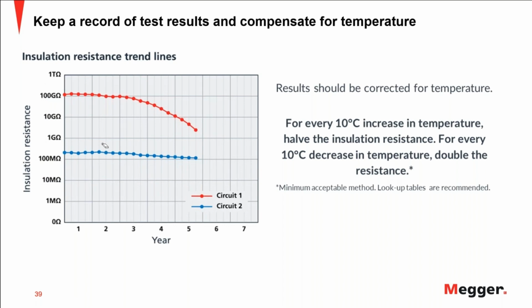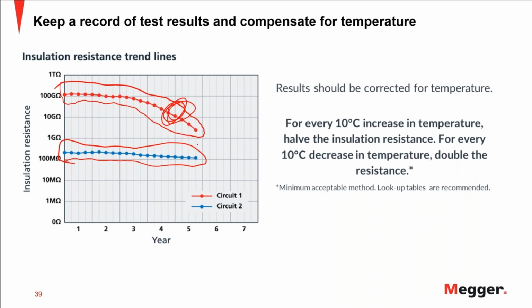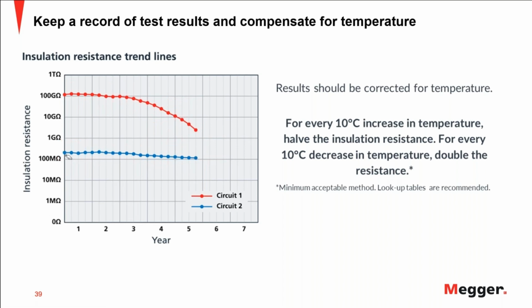And lastly, you want to trend the value, so it's not a matter of running the test and not taking note of it. You want to test, come back after some time and retest, and you want to detect degradation. The way to detect that degradation is by trending the values. You see that this one has a 100 megaohm value, very steady. This one has a much higher value, but at some point it starts decreasing. It's still better than the 100 megaohms. But if you ask me, this insulation that has a high value but has been decreasing is an insulation that has problems. So that is something to also take into account when reviewing insulation resistance results.